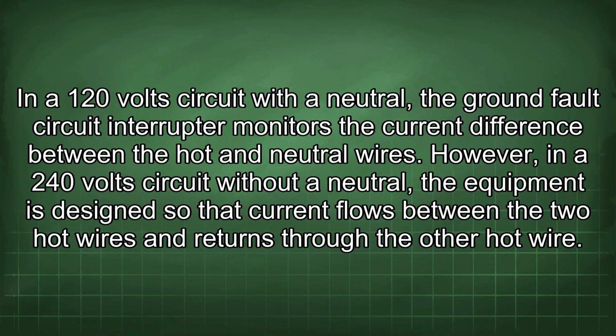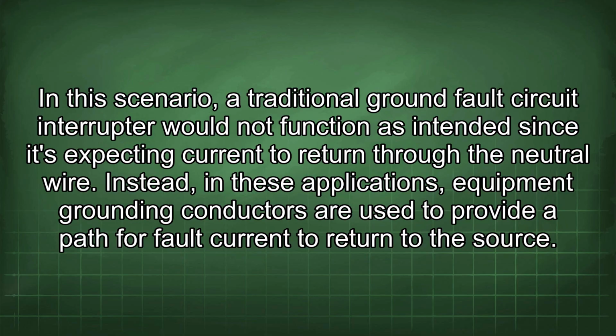In a 120-volt circuit with a neutral, the ground fault circuit interrupter monitors the current difference between the hot and neutral wires. However, in a 240-volt circuit without a neutral, the equipment is designed so that current flows between the two hot wires and returns through the other hot wire. In this scenario, a traditional ground fault circuit interrupter would not function as intended since it's expecting current to return through the neutral wire. Instead, in these applications, equipment grounding conductors are used to provide a path for fault current to return to the source.